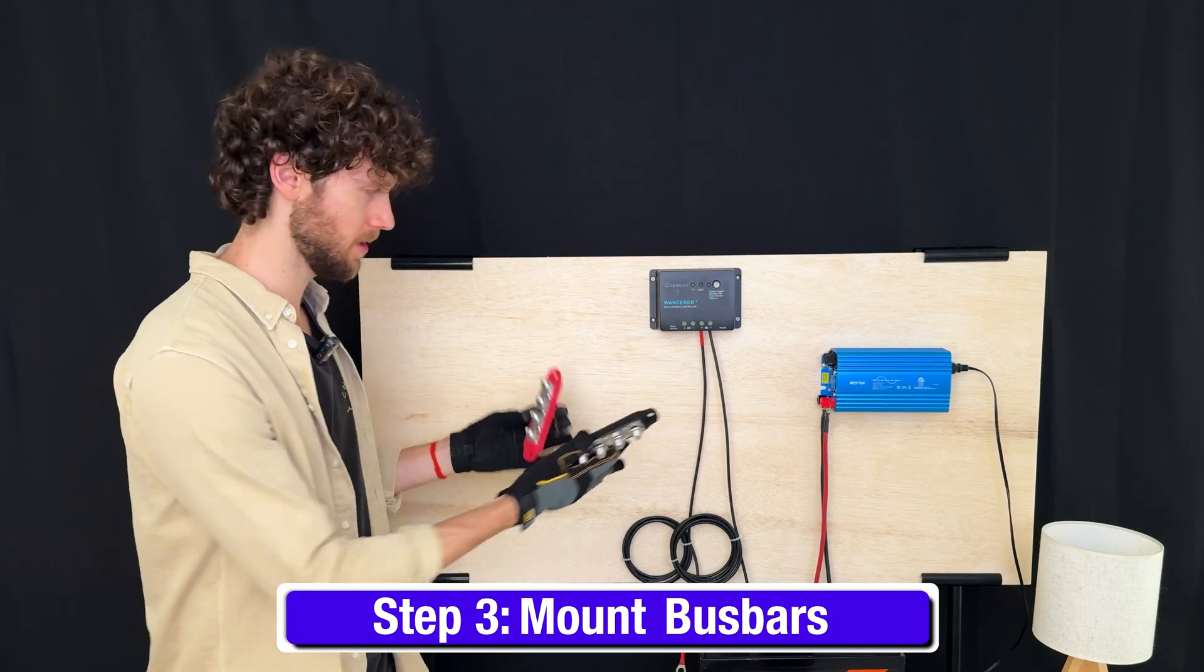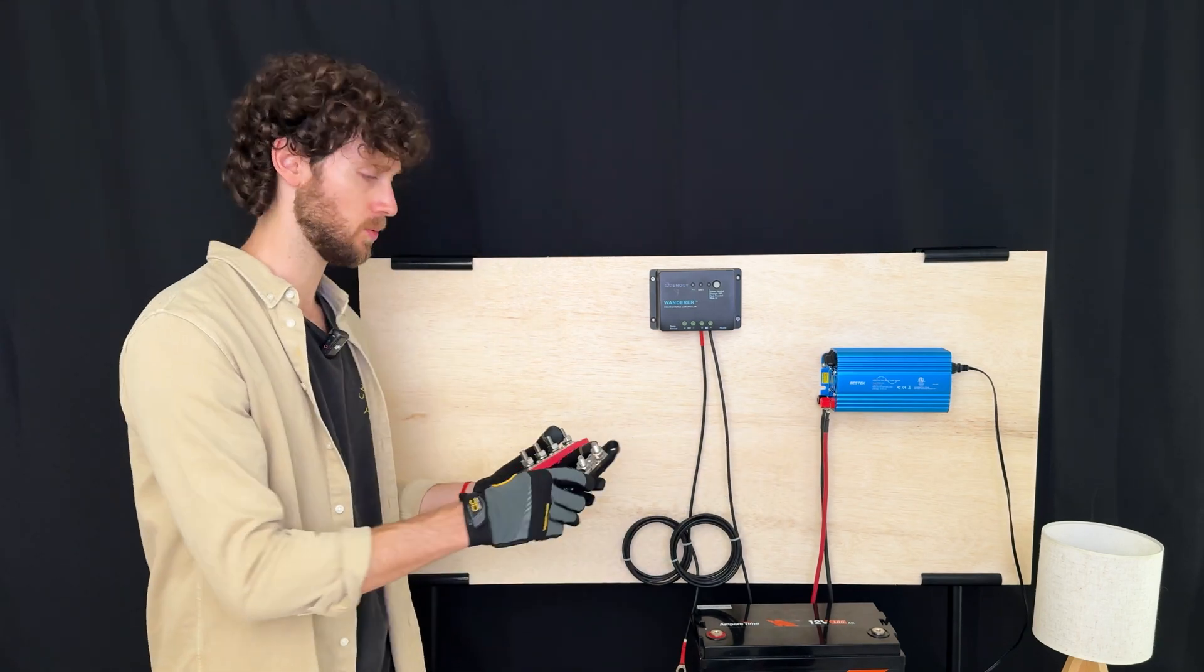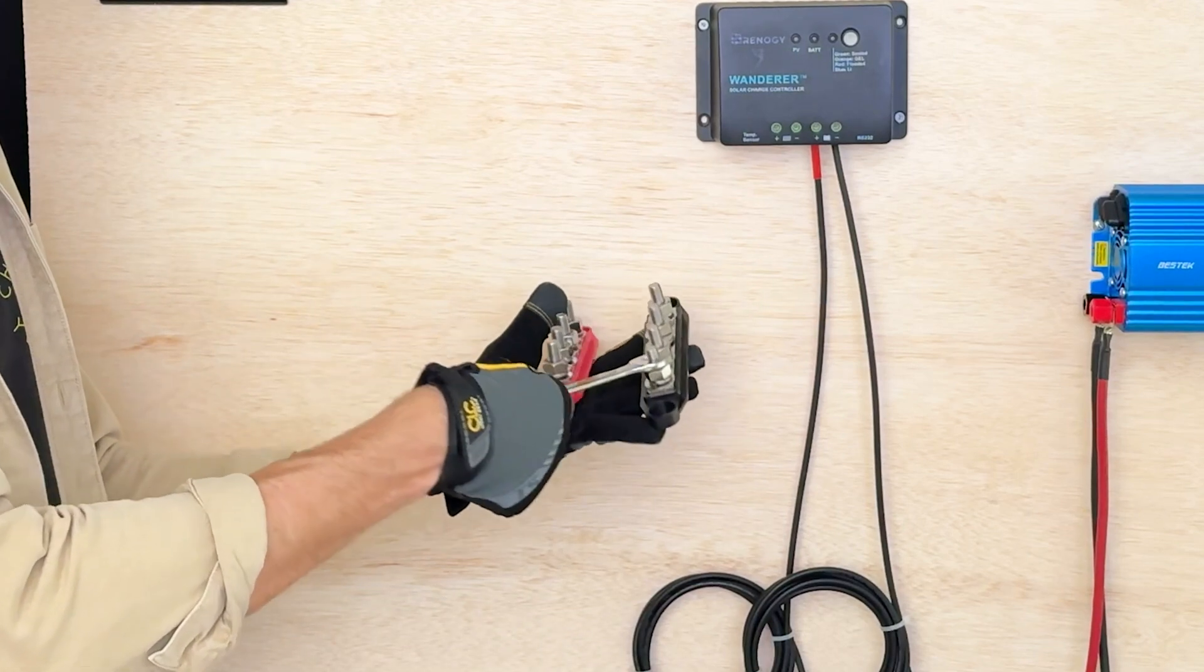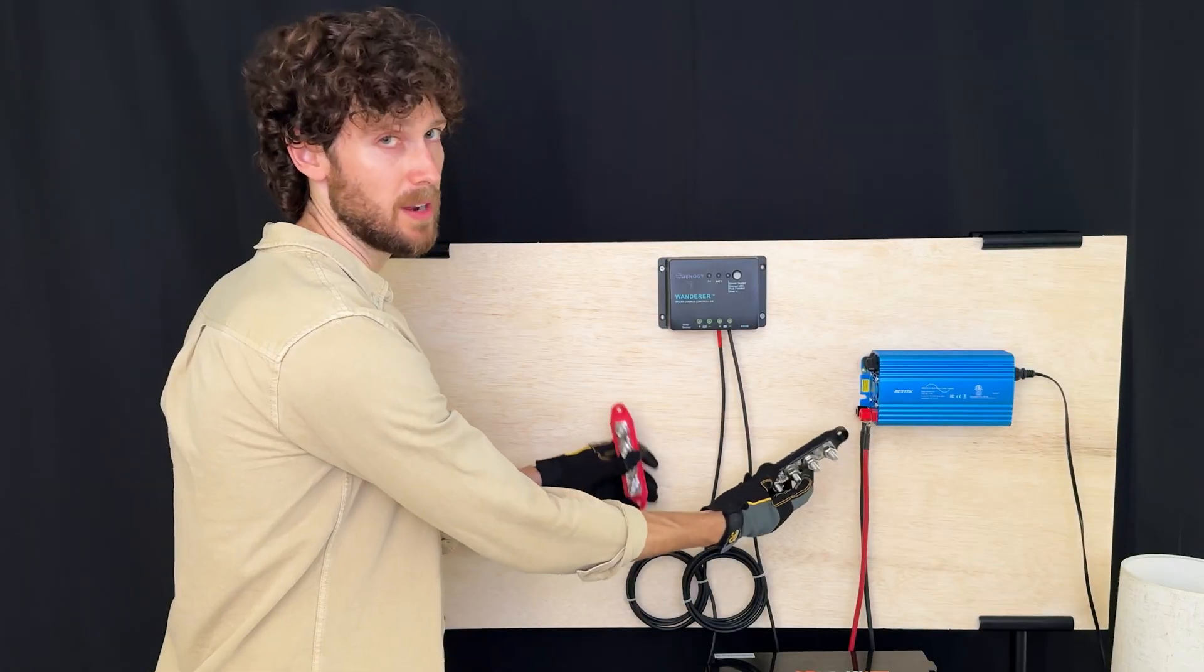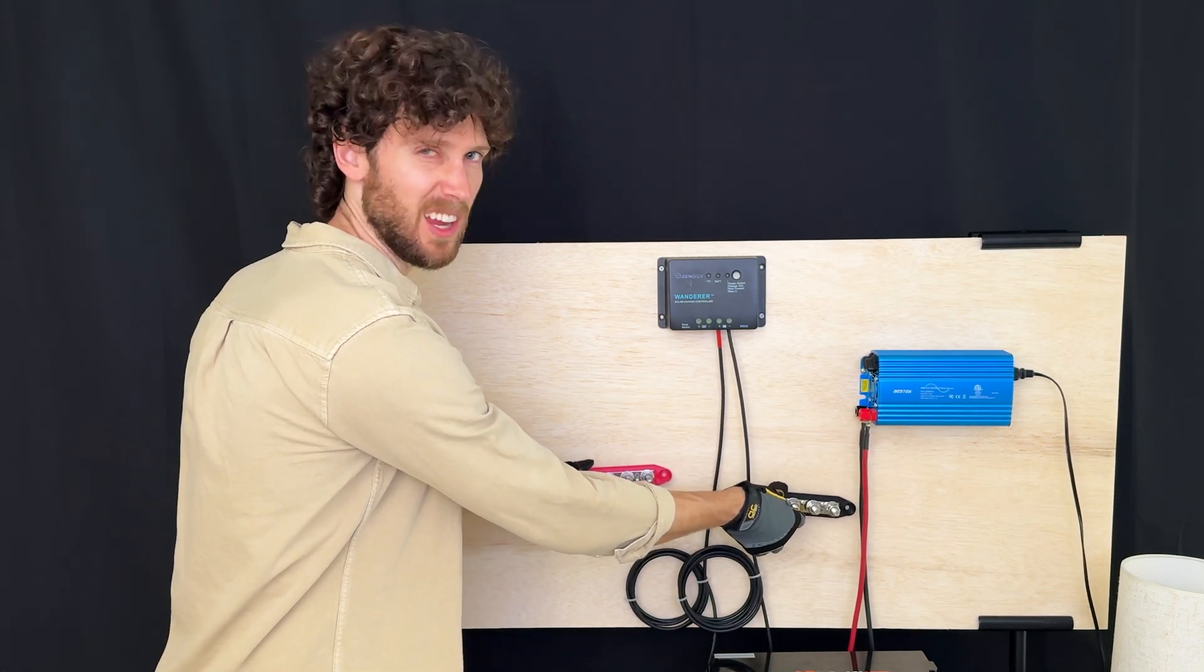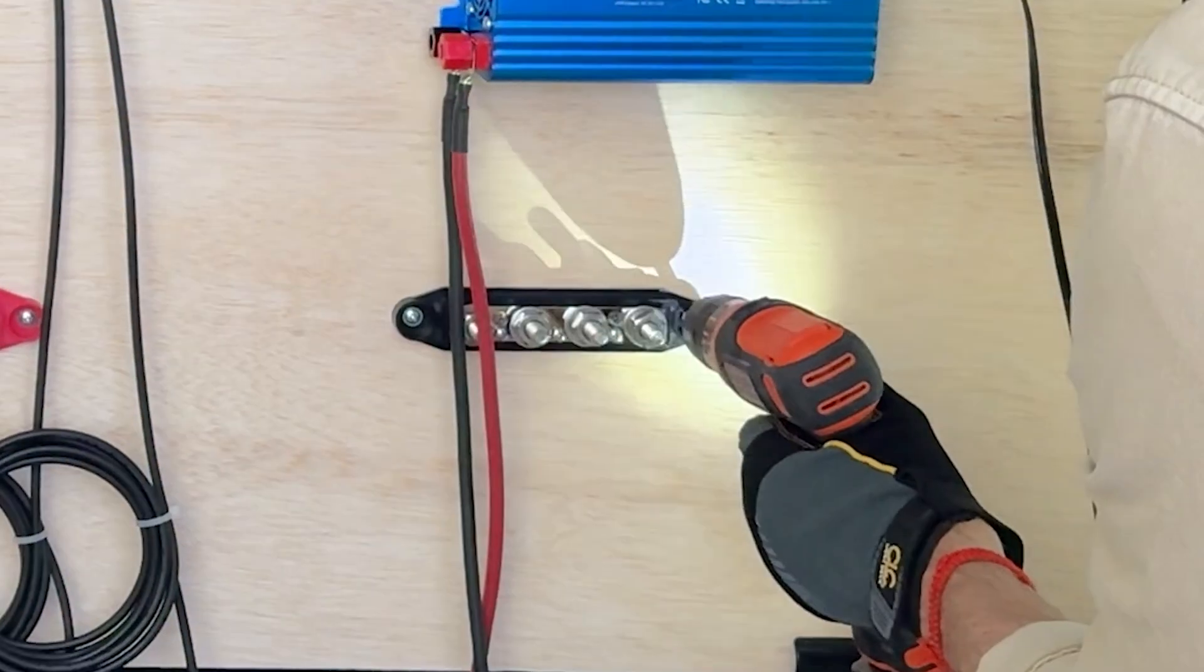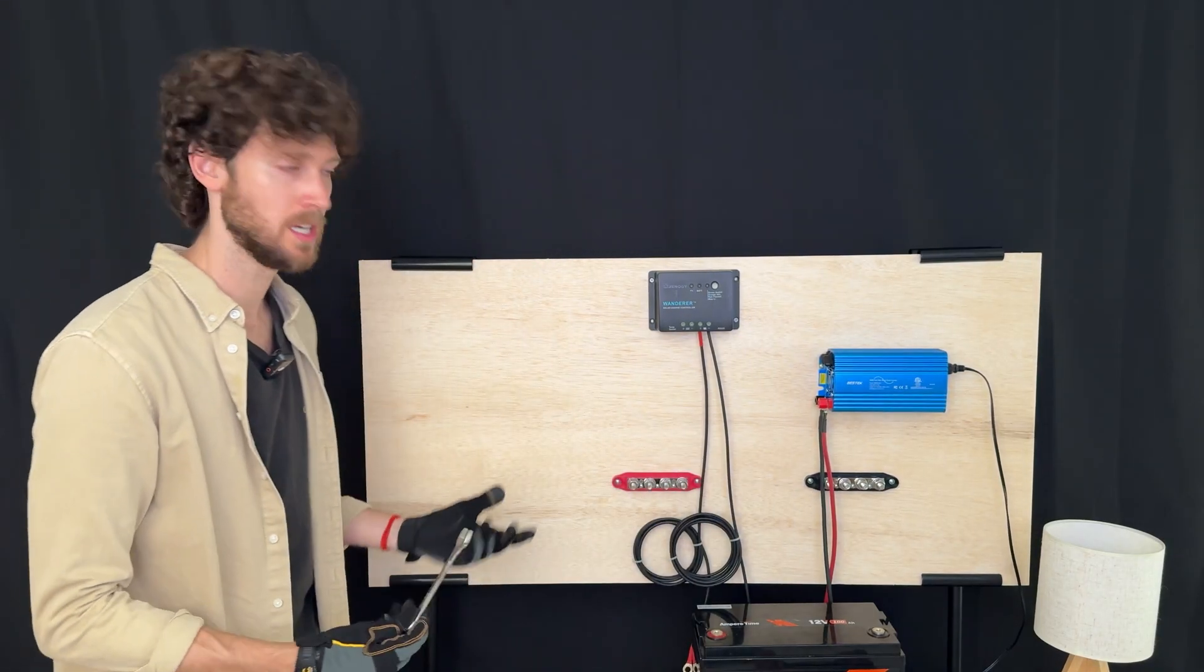Step three is to mount the bus bars to your mounting surface. So you can mount them wherever. You can mount them horizontally, vertically. The one thing I will say is mount them far enough apart that if you're ever working on your system tightening a bolt, that you don't accidentally short circuit your system. If you're unscrewing a bolt with a wrench or something and you touch metal to metal on the positive to negative end because these will be directly connected to the battery. So I'm going to mount them a little far apart just to prevent that from happening. I think I'm going to mount them horizontally, like right here. That looks good. Okay, they're mounted.